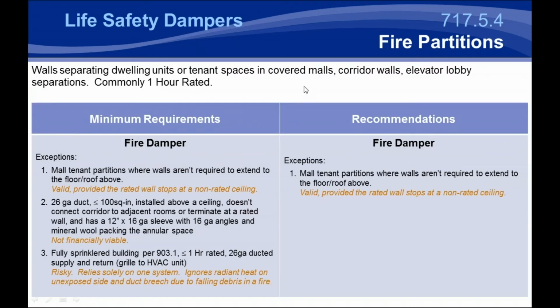Fire partitions are going to be the next restrictive type of assembly we talk about, and basically these are walls separating dwelling units or tenant spaces in covered malls, and most typically they're corridor walls or elevator or lobby separations. They're commonly 1 hour rated, and because they're fire partitions, that's about the lowest fire rating you can get. Some valid exceptions we feel for penetrations in fire partitions is when they're mall tenant partitions that aren't required to extend completely from the floor to the ceiling above or the roof above. Basically, they're not deck to deck, and that's valid because the fire is just going to spread above that area that's not protected by the fire partition.